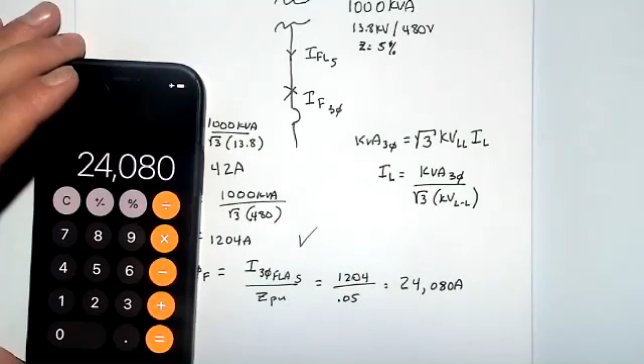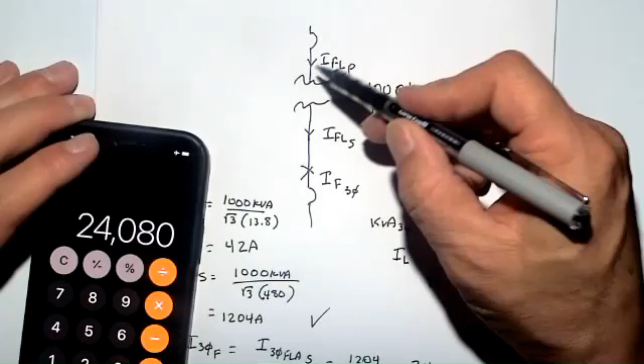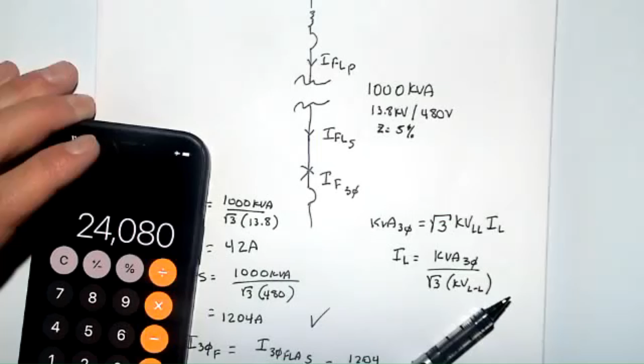Now, on the next page, we're going to talk about the infinite bus, and why we do not calculate the fault current on the primary side. The reason we can't is we don't know what the impedance back here is. So let's talk a little bit about that. What does an infinite bus mean? An infinite bus basically says that we have zero impedance all the way looking back to the source. And we know that's not exactly true. Of course it's not true.